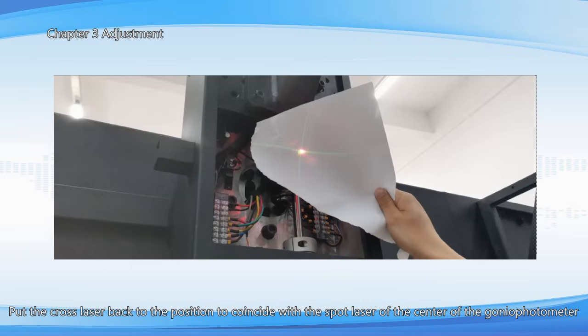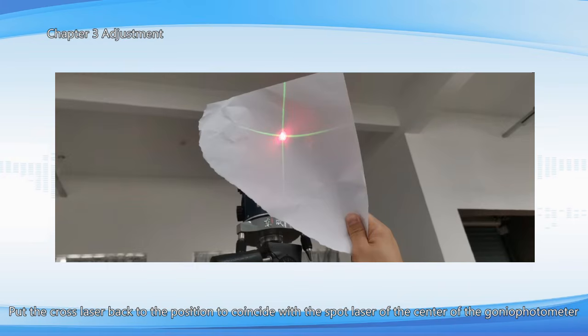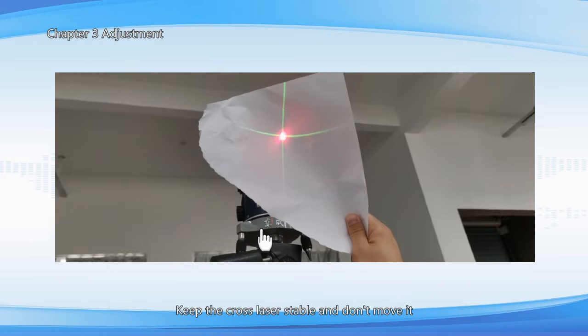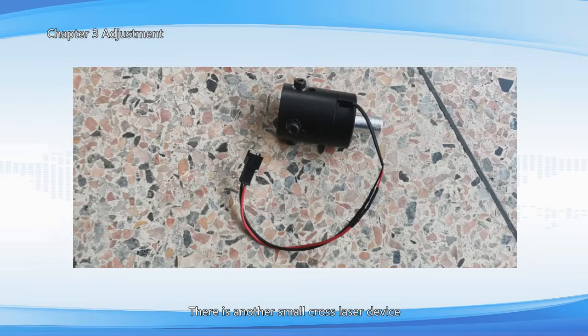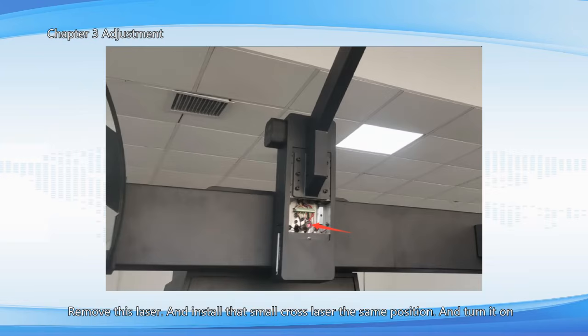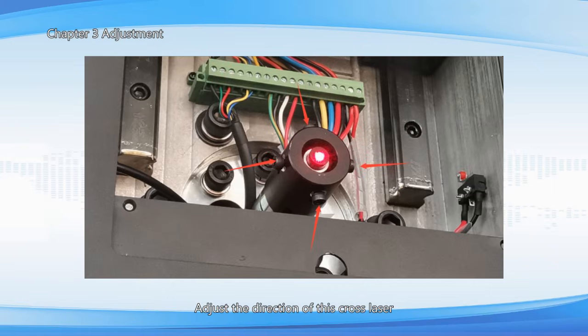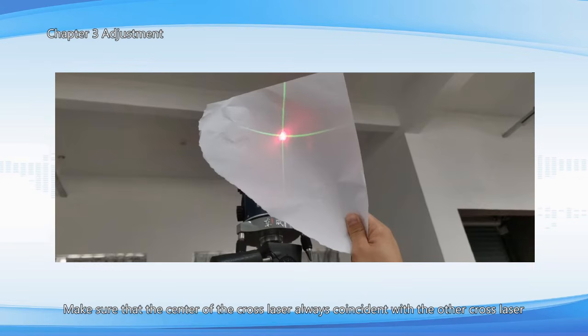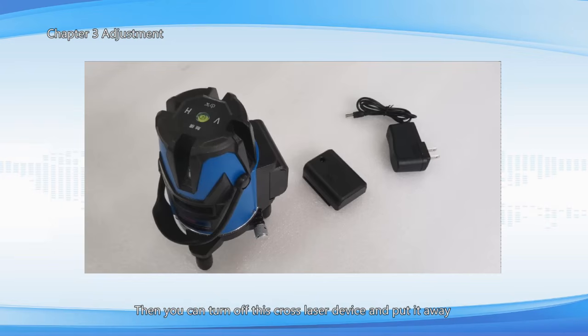Put the cross laser back to the position to coincide with the spot laser of the center of the gonio-photometer. Keep the cross laser stable and don't move it. There is another small cross laser device. Remove this laser, and install that small cross laser in the same position. And turn it on. Adjust the direction of this cross laser. Make sure that the center of the cross laser is always coincident with the other cross laser. Then you can turn off this cross laser device and put it away.